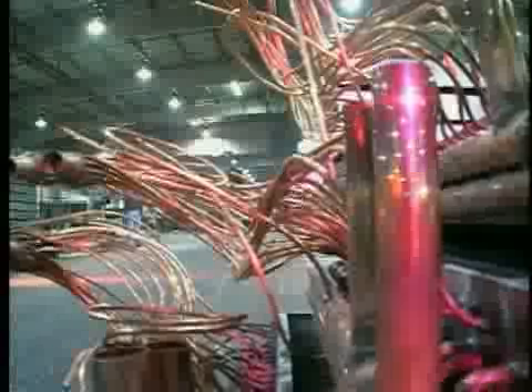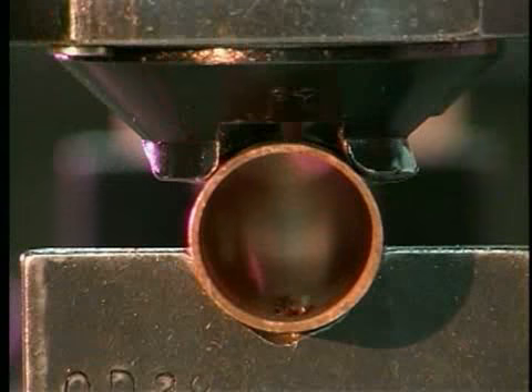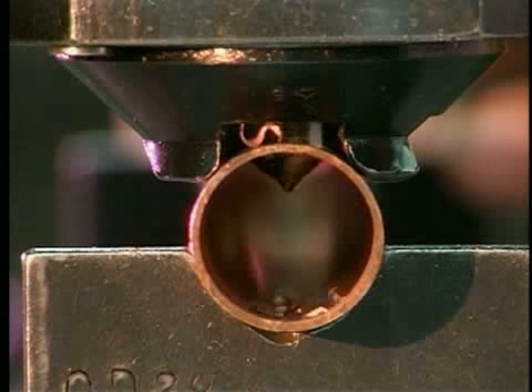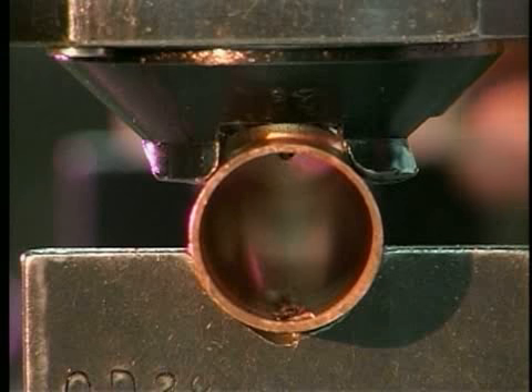They pay attention to the details to ensure reliability with heavy wall seamless drawn copper headers with spun or die-formed end closures for added strength. The coil tube connections are made through drawn holes for good bonding during the brazing process. All joints are brazed with select high-temperature copper brazing alloys by experienced brazers.